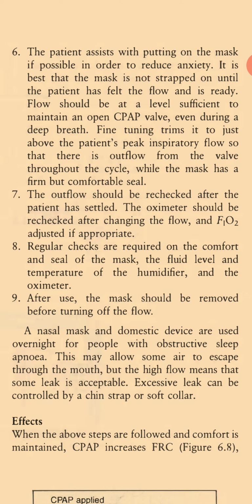Fine tuning trims it to just above the patient's peak inspiratory flow so that there is outflow from the valve throughout the cycle, while the mask has a firm but comfortable seal. The outflow should be rechecked after the patient has settled. The oximeter should be rechecked after changing the flow and FiO2 adjusted if appropriate. Regular checks are required on the comfort and seal of the mask, the fluid level and temperature of the humidifier, and the oximeter. After use, the mask should be removed before turning off the flow.